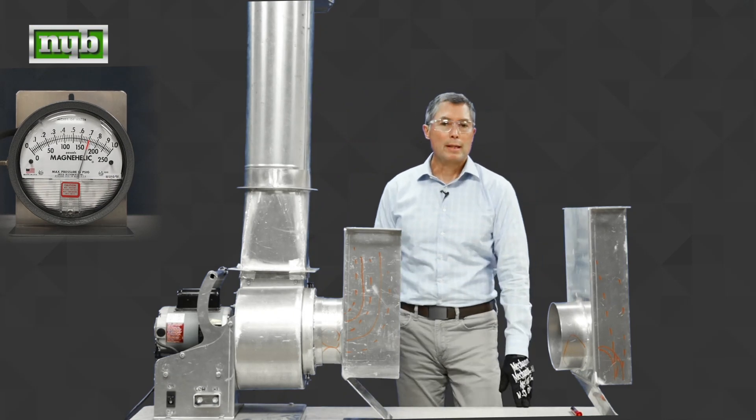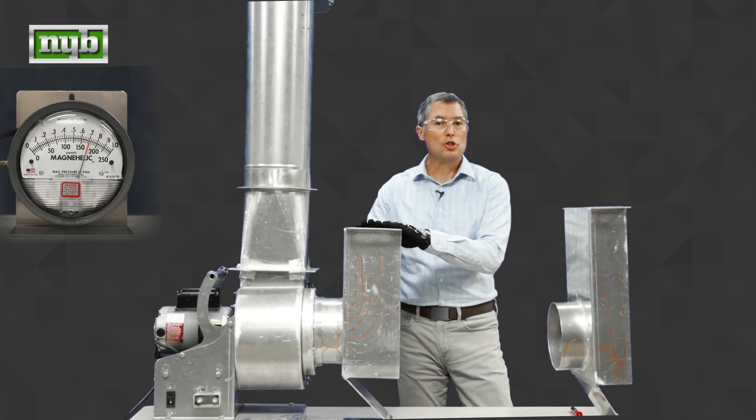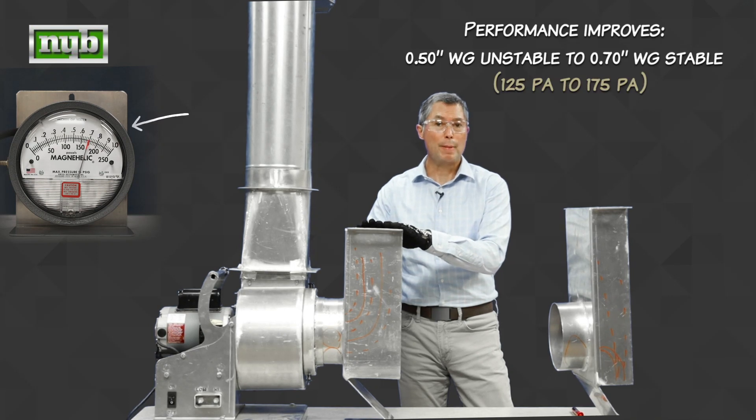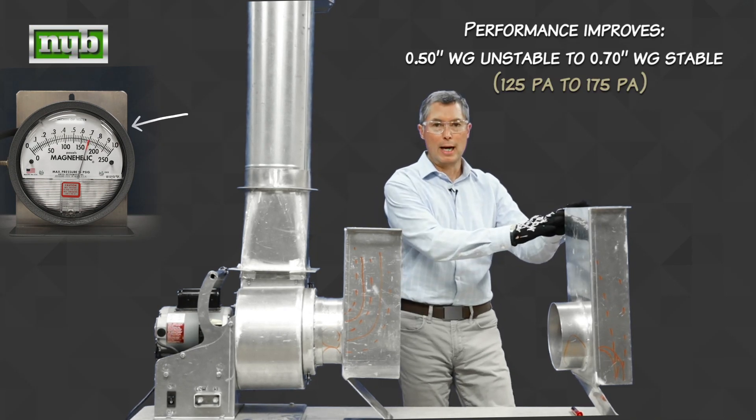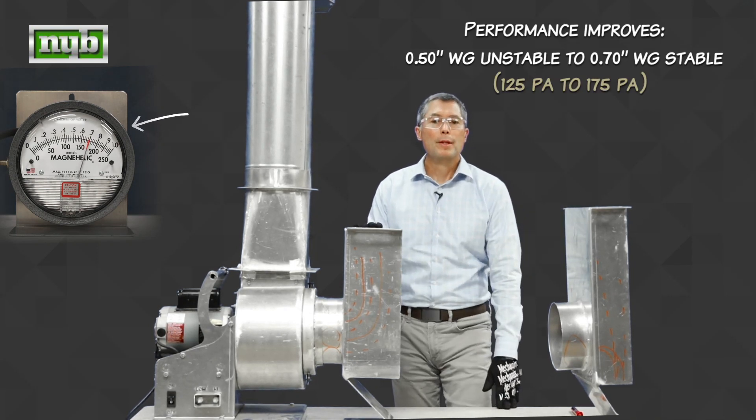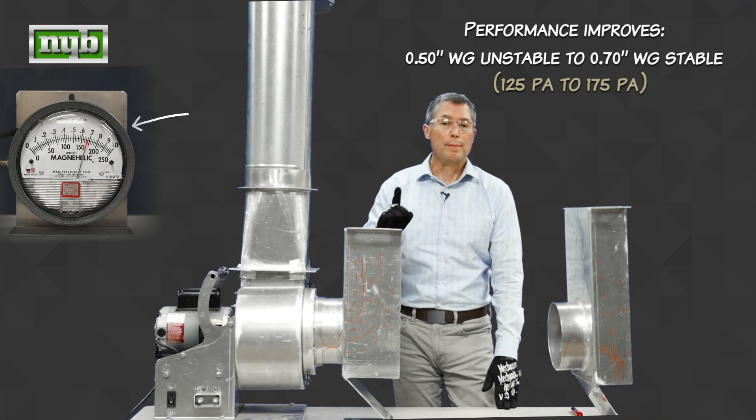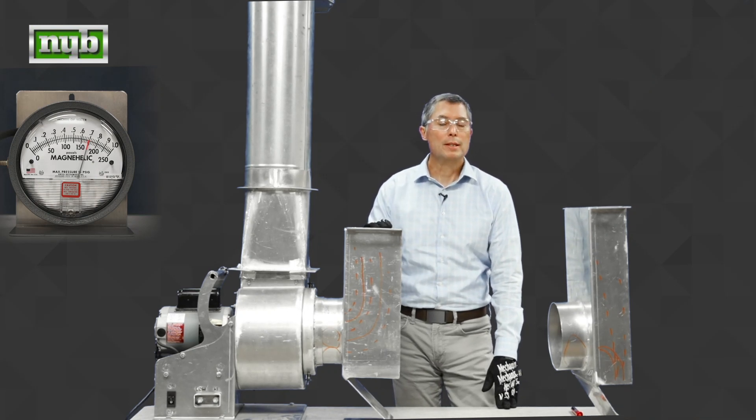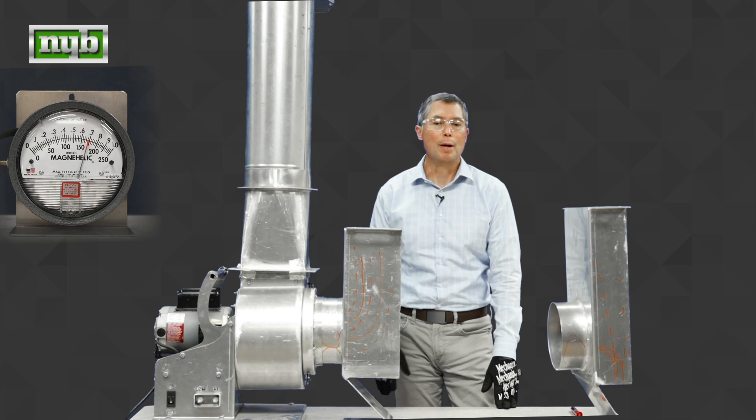Okay, looking at the Magnehelic, you'll notice that there's a substantial improvement in performance with this box design over this box design. Secondly, the needle or the marker on that Magnehelic gauge is much more steady. It's not bouncing up and down.